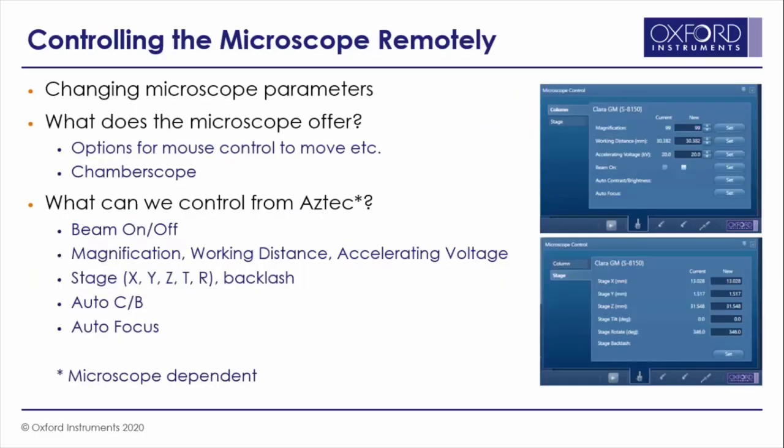Different microscopes offer different control systems. Some of these include hands-on controls like joysticks or trackboards, and others are entirely software-based. Most have options for software or mouse-based control and therefore can be used via remote connection, although the experience of doing so may be slightly different. Many microscopes also have chamberscopes that can be viewed directly in their interface, and these are invaluable particularly when you are making big moves with your sample. Aztec actually includes functionality that allows you to control many of the microscope parameters directly — parameters such as magnification, accelerating voltage, and stage positions can all be controlled directly via the microscope control panel at the bottom right of the Aztec interface.